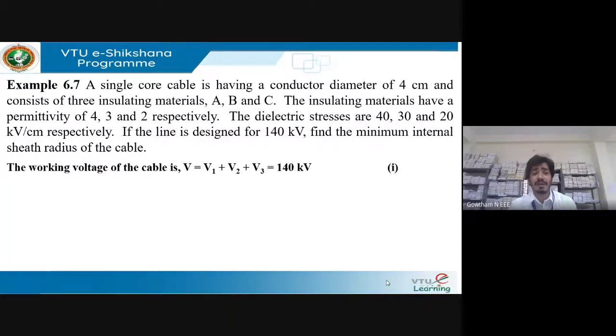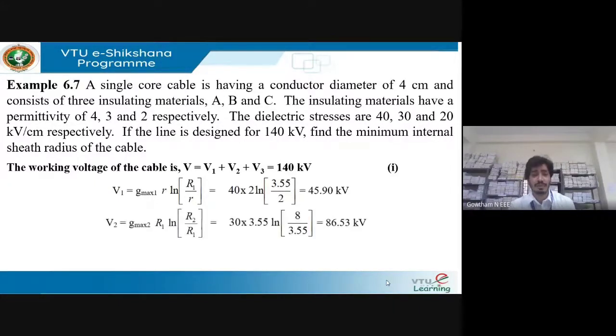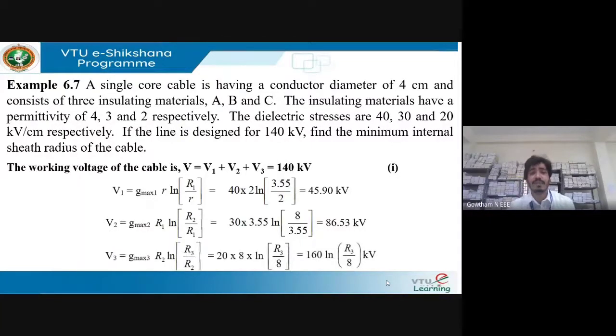The working voltage of the cable is given as 140 kV, so V = V1 + V2 + V3. V1 = Gmax1 × r × ln(R1/r). After substituting Gmax1 and r, V1 = 45.90 kV. V2 = Gmax2 × R1 × ln(R2/R1). Substituting Gmax2 and R1, V2 = 86.53 kV.